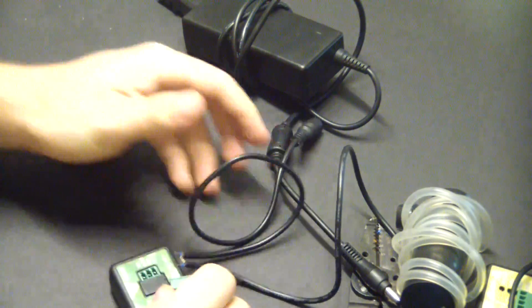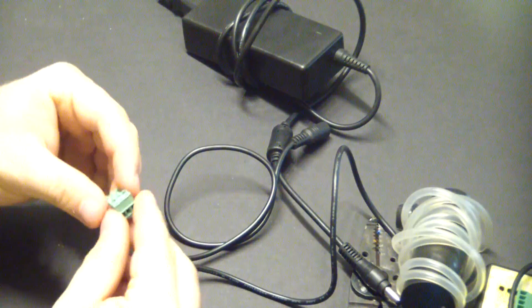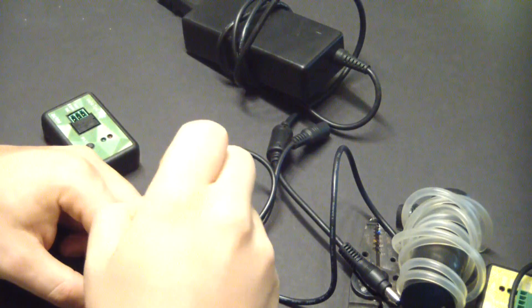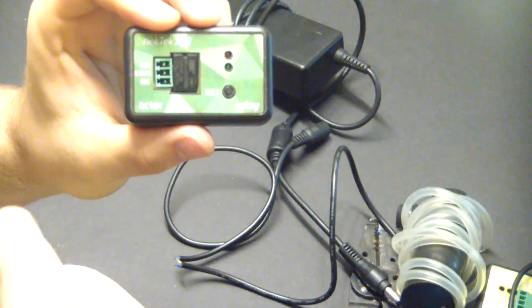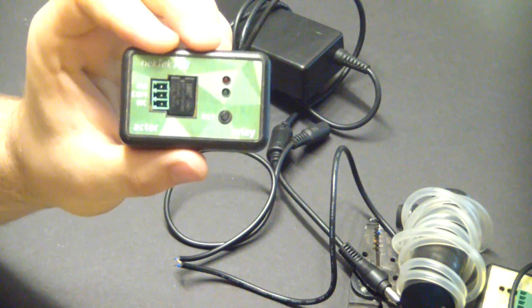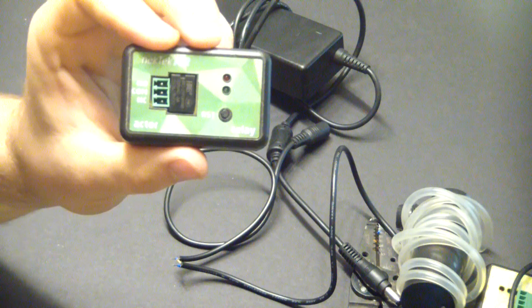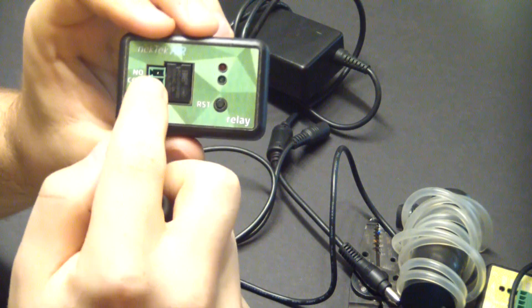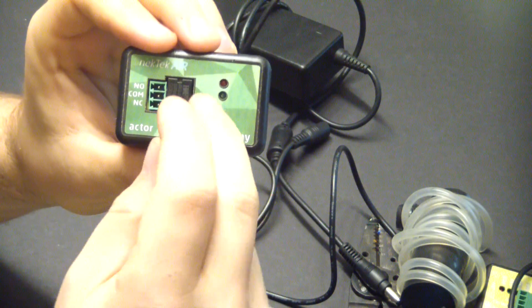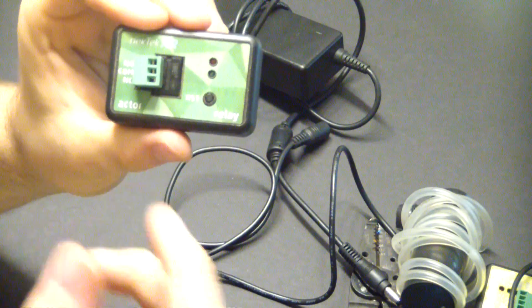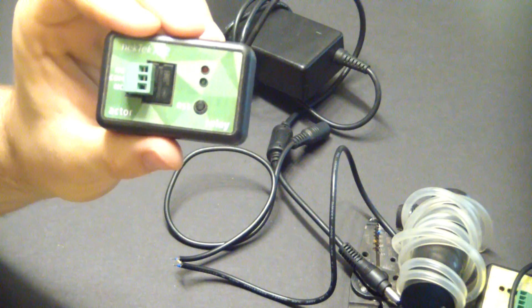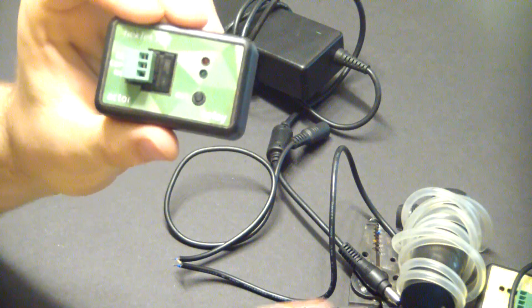I'm going to take the terminal block out of the relay actor and open it up with the screwdriver. We want the pump to be off when there's no power to the relay actor, so we want normally open. Normally open means it's open when it's off and then when it's activated it closes.